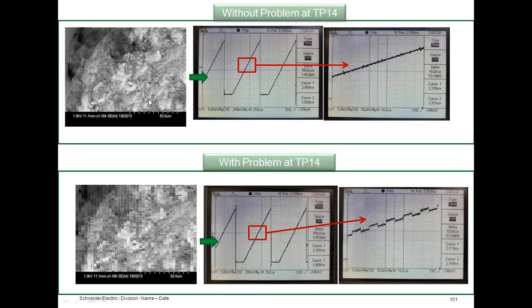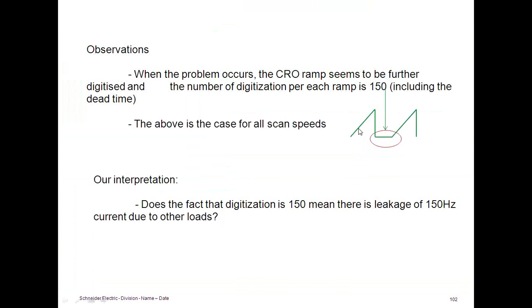So the high frequency zero sequence harmonics coming from the computers go through the computer cables to ground, and from ground it's coming back to this microscope. If you look at the ramp of the second image and blow it up, you can see the ramp has a 150 hertz disturbance. 150 hertz is the harmonic disturbance. So where is this harmonic coming from? It's coming from the computer loads linked to the same UPS on which we have this microscope. The computer loads are pumping harmonics through these cables into the ground system, and the ground system is giving feedback to this microscope. So the microscope malfunctions.